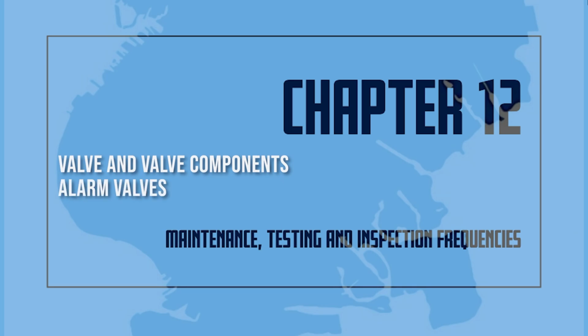Alarm valves. Exterior alarm valves shall be inspected monthly to ensure the gauges indicate a normal supply water pressure is being maintained. The valve shall be free of physical damage and all valves shall be in the appropriate open or closed position. The retarding chamber or alarm drain shall be in good condition without leaks. All alarm valves and their associated strainers, filters, and restricted orifices shall be inspected internally every 5 years unless tests indicate a greater frequency is necessary. Check valves shall be inspected internally every 5 years to verify that all components operate correctly, move freely, and are in good condition.